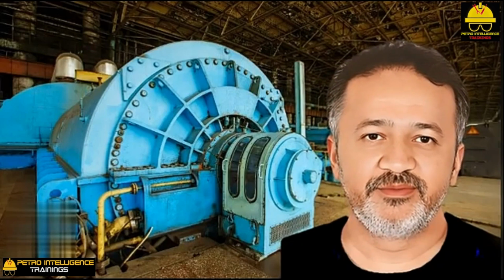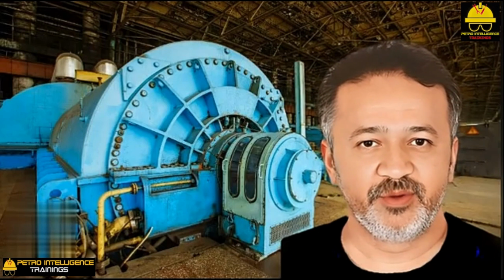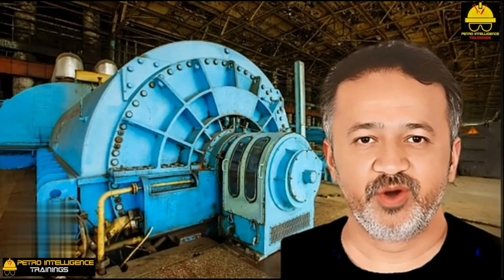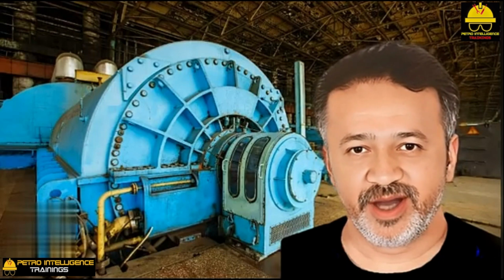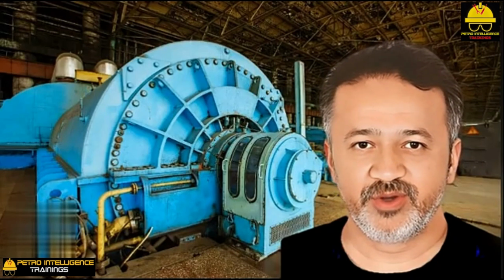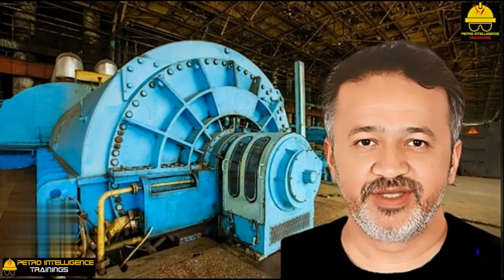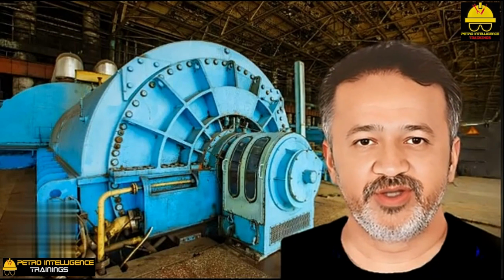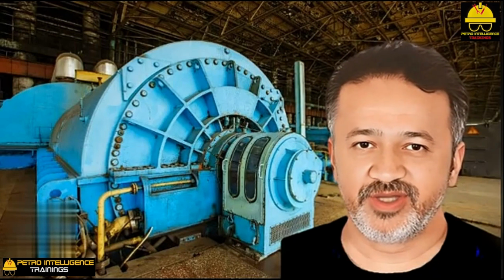Steam rack. On larger steam turbines, we have automatically, rather than manually, operated horsepower valves. The mechanism that controls the movement of the horsepower valves is called a steam rack. If you have a large steam turbine driving a compressor, you have likely seen such a steam rack. A horizontal rod extending across the width of the turbine has a half-dozen cams fixed along its length. These cams lift and lower, in sequence, plungers attached to the horsepower valves. Watch these plungers in action.